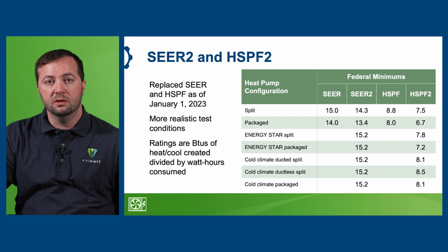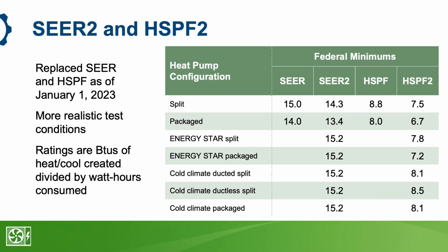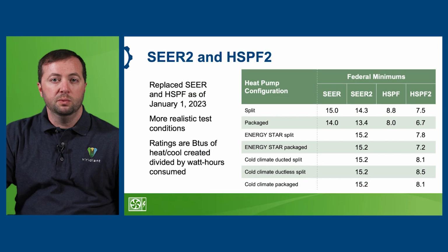As a result, the SEER 2 ratings for cooling equipment will be a bit lower, about 5%, than SEER ratings in most cases. And similarly, for heat pumps, that HSPF 2 rating will also be lower, about 15%, than the HSPF ratings. For example, a heat pump with a SEER rating of 14 and an HSPF rating of 10 would likely get a SEER 2 rating of about 13 and an HSPF 2 rating of about 8.5. The difference between SEER 2 and HSPF 2 ratings from SEER and HSPF ratings will vary from one equipment to another, but it mainly depends on the system type, such as split system, single package, etc.